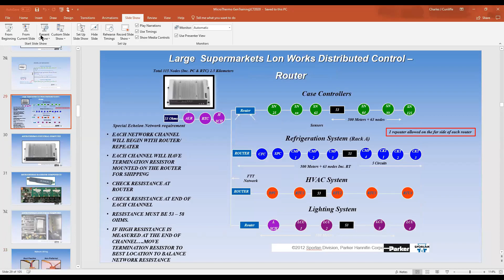So again, it is not a network termination, it is not an end of the line resistor. What we're doing is balancing 53 ohms, 53, 53, 53, 53, and we want that envelope to be somewhere no lower than 53, no higher than 58. If it's lower than 53, you might have a breach somewhere. If it's higher, if you've got 75, 80, or 100, you probably have a wire that's skinned somewhere, or you've got a board that's grounded, and that's why the resistance is too high.